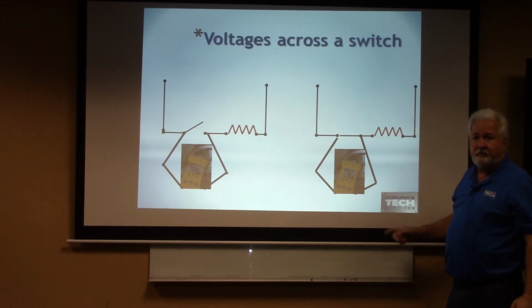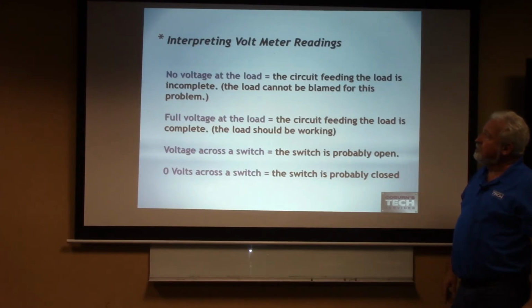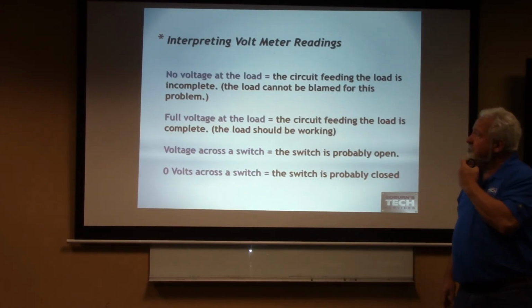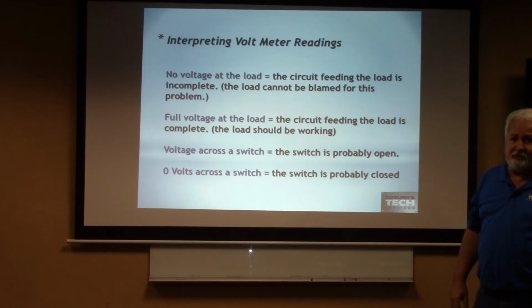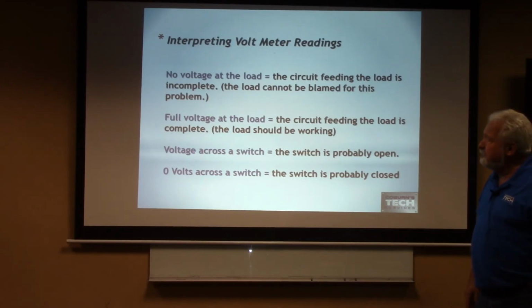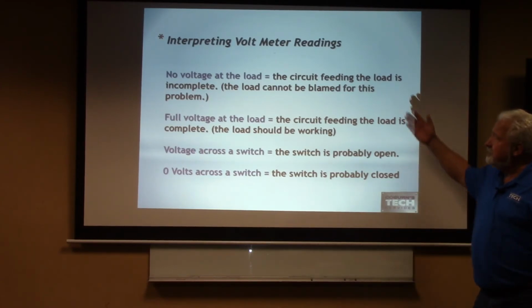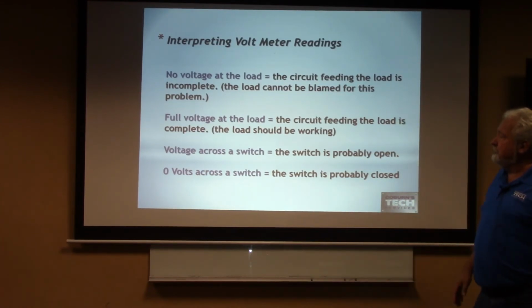Everybody good? All right. So, interpreting the voltage. No voltage at the load. If you don't have any voltage at the load, you can't say that the load is bad. You can't say that the motor's not good because the voltage is not there. Something else is not allowing the voltage to get there. Full voltage to the load: the circuit feeding the load is complete. The load should be working. Voltage across the switch is probably open. 0 voltage across the switch is probably closed. Everybody good with that? Sweet.